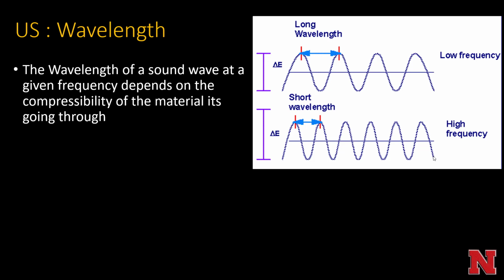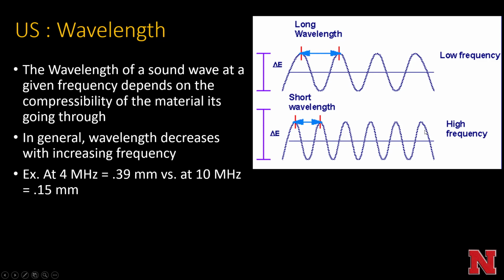Wavelength: the wavelength of a sound at a given frequency depends on the compressibility of the material it's going through. Here's an example of a low frequency wave and a high frequency wave. The low frequency wave has a long wavelength versus a short wavelength for the high frequency wave. In general, wavelength decreases with increasing frequency. So at 4 megahertz, the wavelength is 0.39 millimeters, versus at 10 megahertz, a much higher frequency, the wavelength is shorter at 0.15 millimeters.